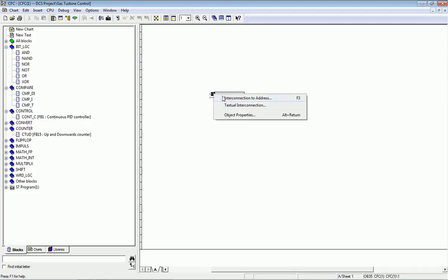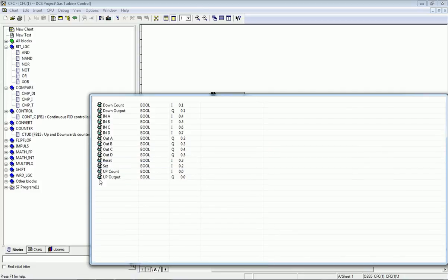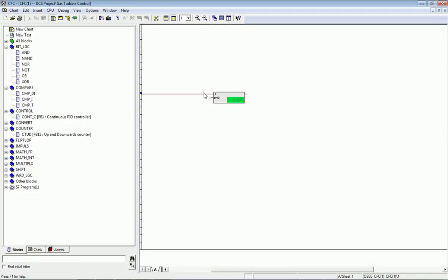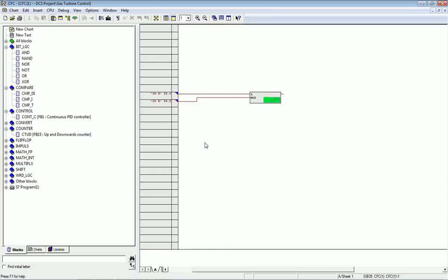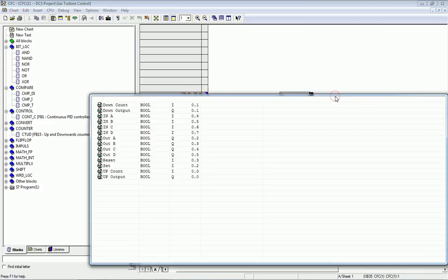To assign inputs to the AND block, I right-click on an input and select 'Interconnection to Address.' The symbolic addresses we assigned from the distributed I/O modules appear here. From this address list I assign input A and input B. On the left side in the CFC chart, the interconnection automatically takes addresses I0.4 and I0.5, which were assigned in the distributed I/O system. On the right side I assign the output addressing via interconnection.